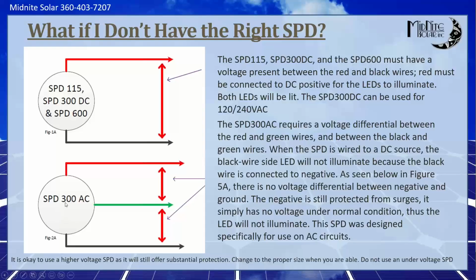And we just got so many calls asking if there's something wrong with their SPD. We went ahead and made the DC model, which all three models now, the 115, the 300 DC, and the 600, use voltage between the red and the black, so you get both LEDs to light up. So that's the difference between the two. You certainly can use an AC on a DC system. There is no difference from an AC or DC standpoint. The only difference would be if you put an SPD 300 AC on a PV array, you'd only have one LED. That's kind of the gist of it, if you will.